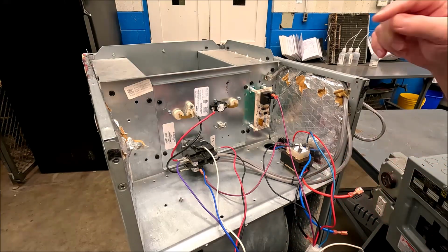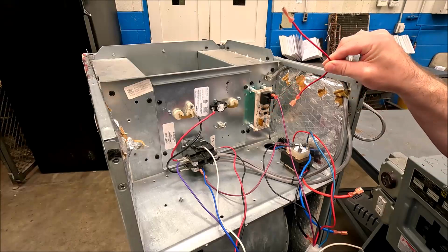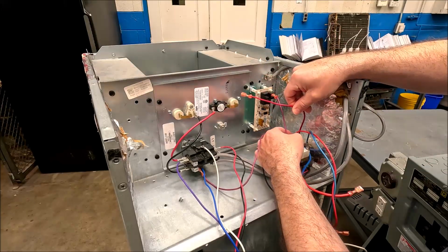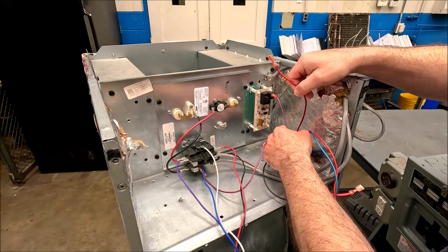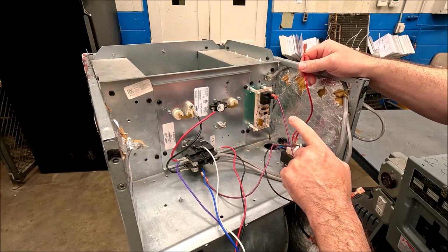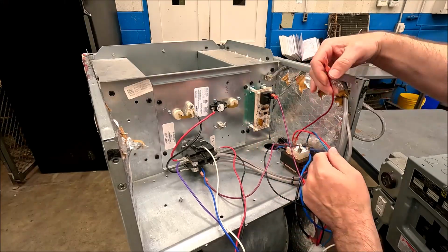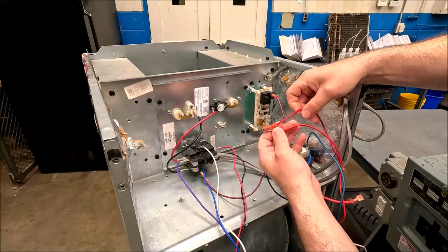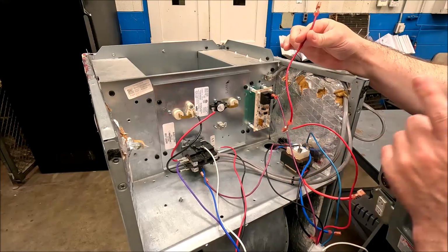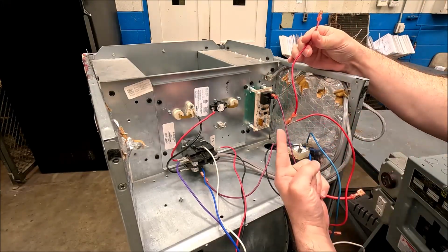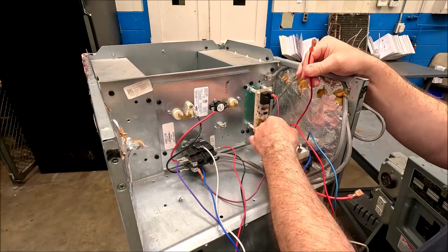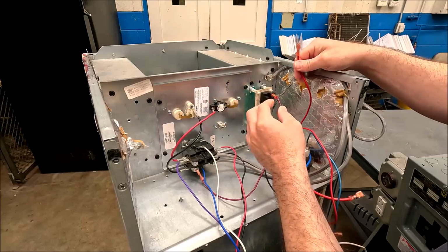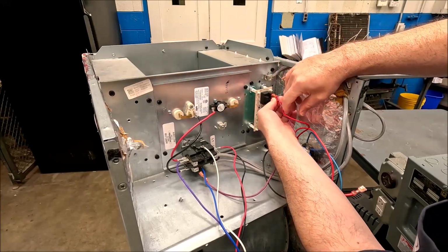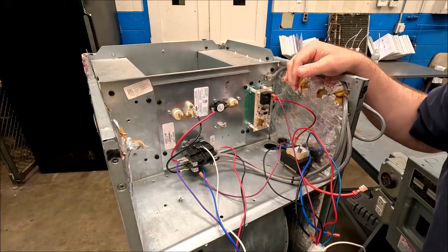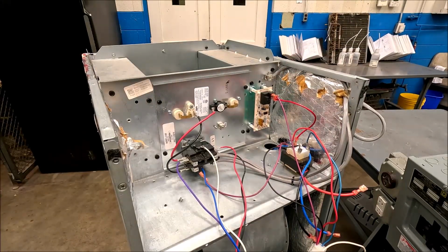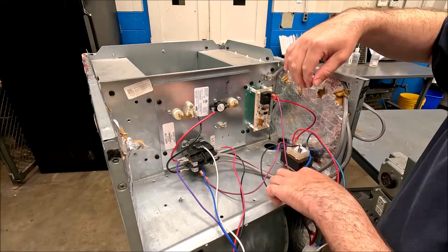One more high voltage wire. This is going to be off of the male plug where it hits the transformer on that L1. This is where I told you, if you're following the flow from power to the blower motor, that connection right here, if you imagine it not even hooked up to the transformer. We're not trying to power the transformer with this wire. We're trying to get L1 into the blower relay. So that's the wire we're putting here, off of the high voltage of the transformer into the normally closed for the blower relay. All right, with that being said, we'll finish with the blower relay.